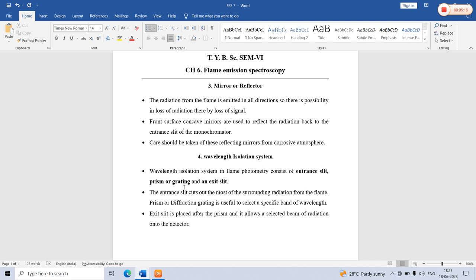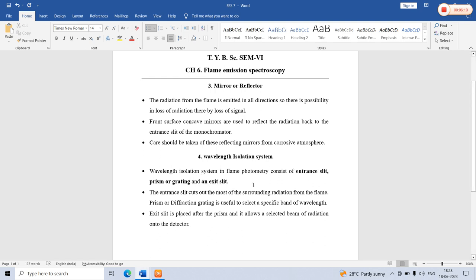The prism or diffraction grating is useful to select a specific band of wavelength. The prism or diffraction grating acts as a monochromator or monochromatic system, which selects a specific band of wavelength. The third component is the exit slit, which is placed after the prism — at the end of the monochromatic system — and it allows a selected beam of radiation onto the detector. This is all about the wavelength isolation system.